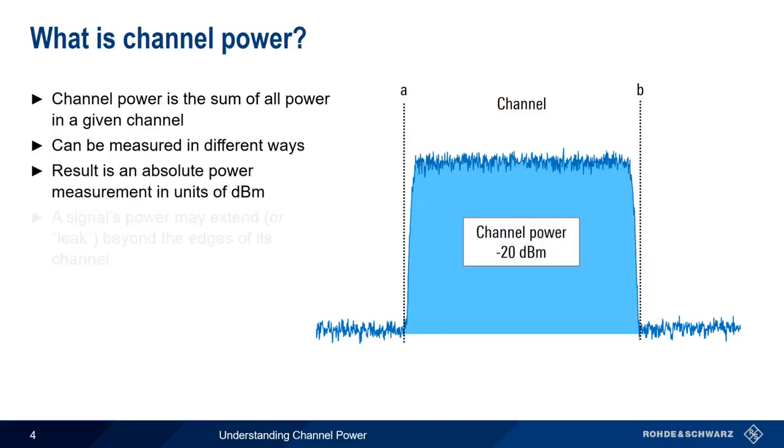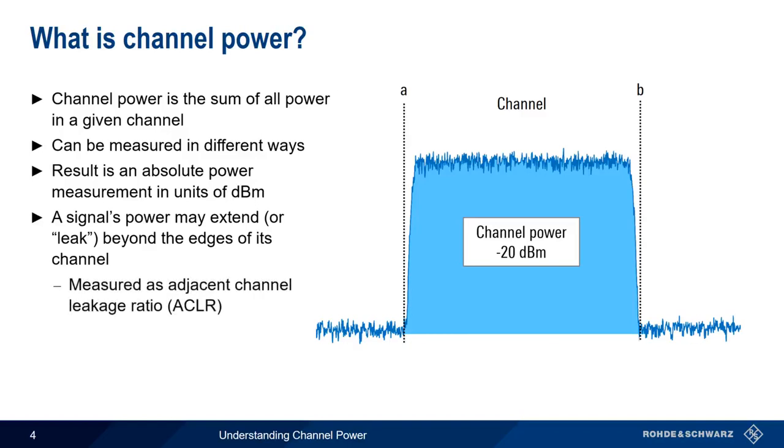Note that in some cases, a signal's power may extend or leak beyond the edges of a channel. The measurement of this leakage, or energy outside of the channel, is called ACLR, or Adjacent Channel Leakage Ratio. ACLR will be covered in a separate presentation.